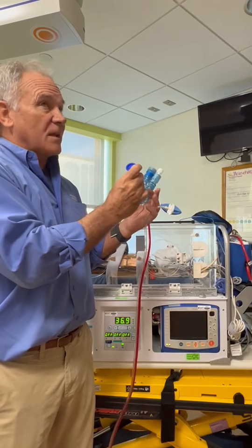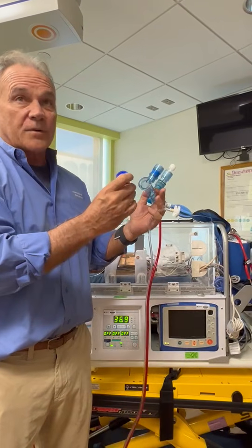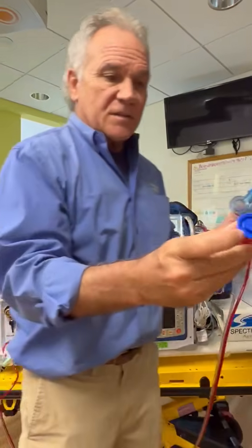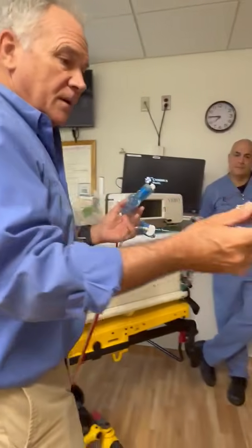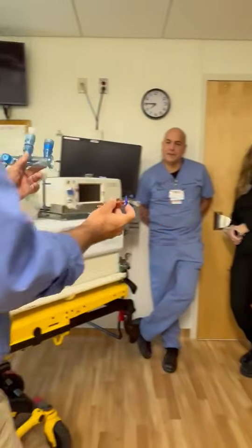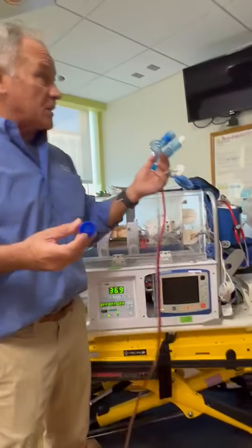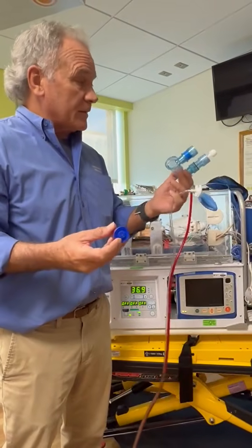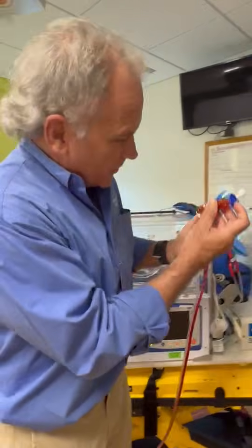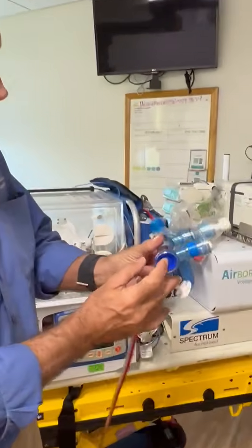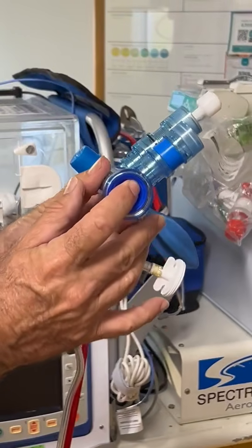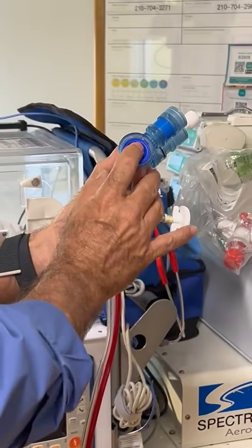But it's different. This is classified as a flow interrupter. Okay. So the gist of it is, I don't know if you can see, it's got this little mini diaphragm here, and it's got a spring. See that little spring right here? It's got that little donut gasket. The flow interrupter was actually the first high frequency ventilator developed out in California. But anyway, the way it works, if you look inside the phasitron, there's a little seal. So when this goes in, this little donut gasket goes down here and seals everything off. It just stops. So that's the inspiratory side.